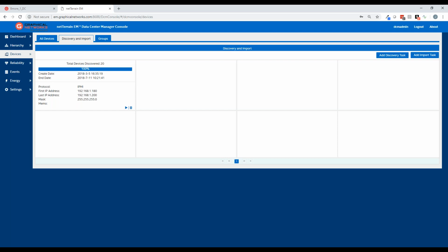If I have smart PDUs, can the tool discover this through SNMP? Yeah, typically, it depends on the smart PDU. Most of my experience with my customers is most PDUs are SNMP enabled or can be SNMP enabled, and that's where you would pull the data, the values that you might want to get. And that could be an aggregate for the whole PDU, or it could be individual, a per-port reading as well.